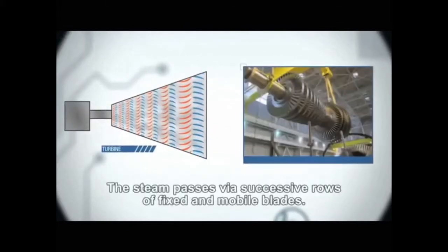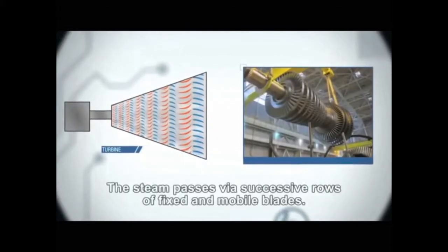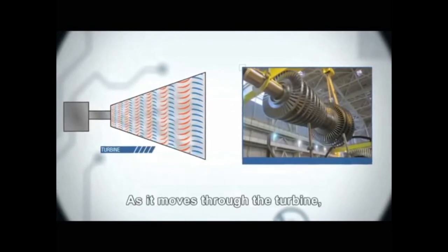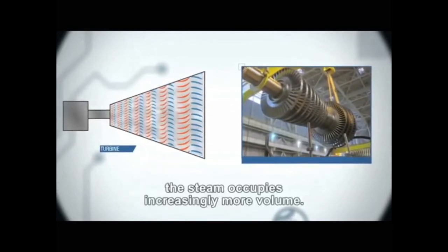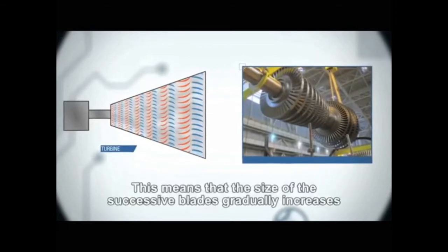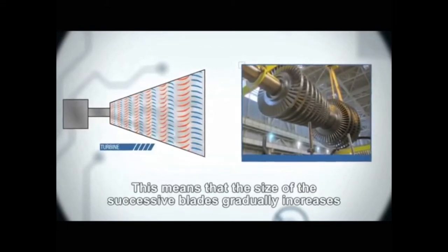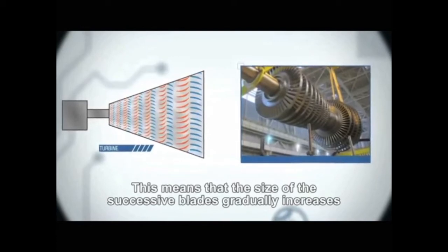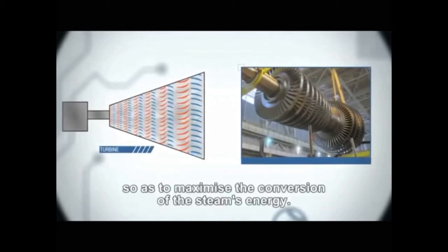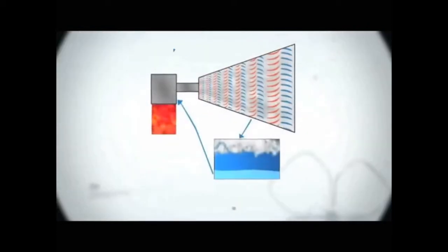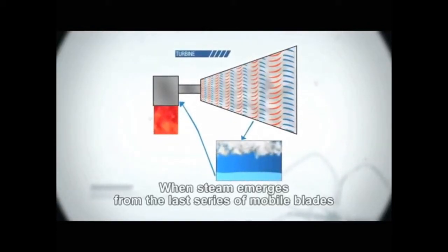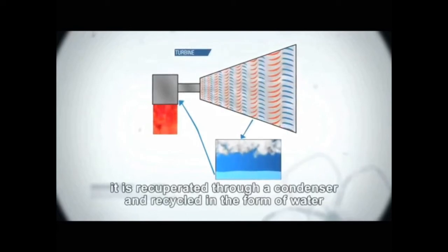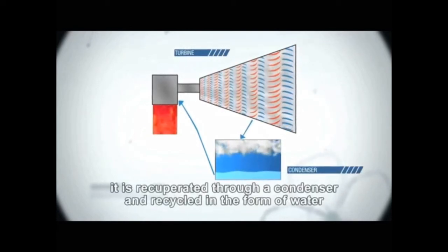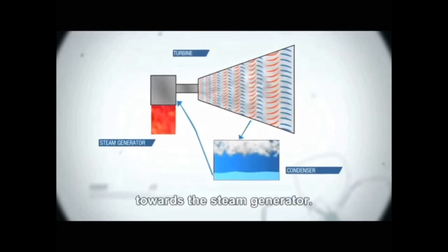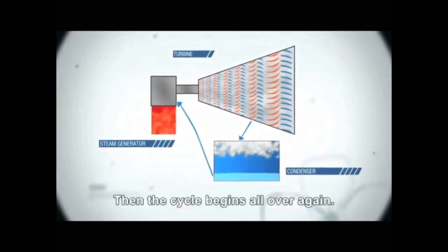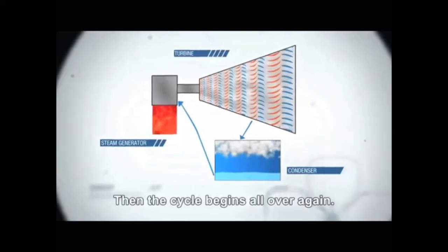The steam passes via successive rows of fixed and mobile blades. As it moves through the turbine, the steam occupies increasingly more volume. This means that the size of the successive blades gradually increases, so as to maximize the conversion of the steam's energy. When steam emerges from the last series of mobile blades, it is recuperated through a condenser and recycled in the form of water towards the steam generator. Then the cycle begins all over again.